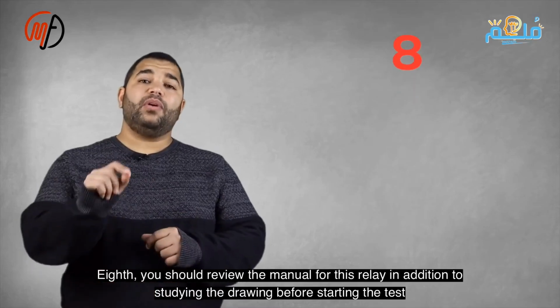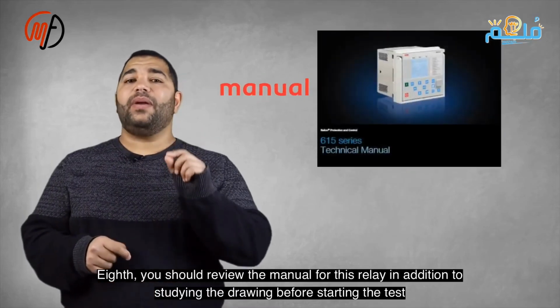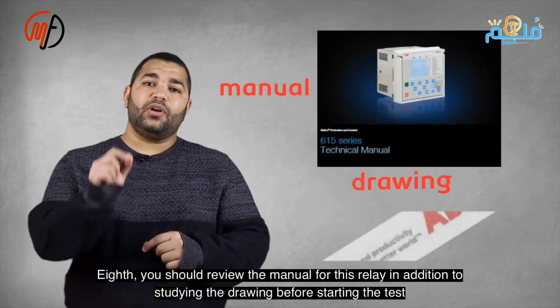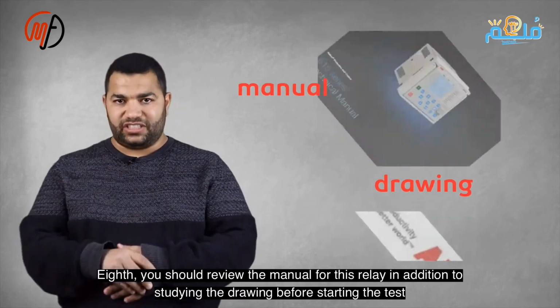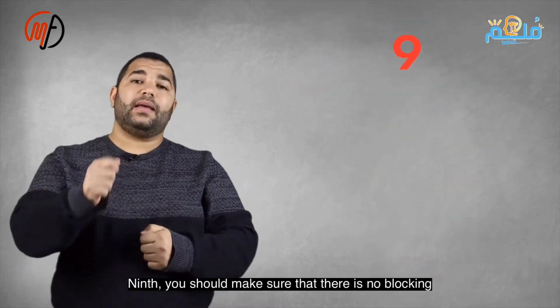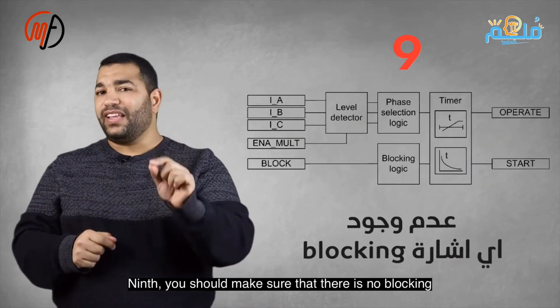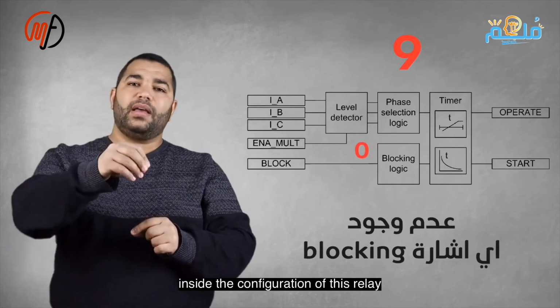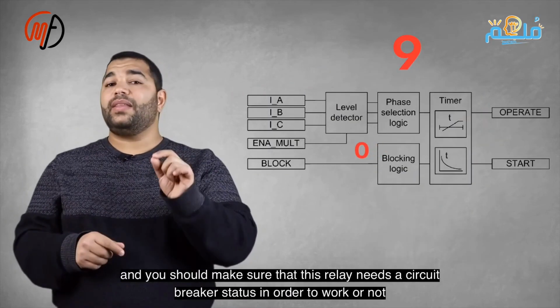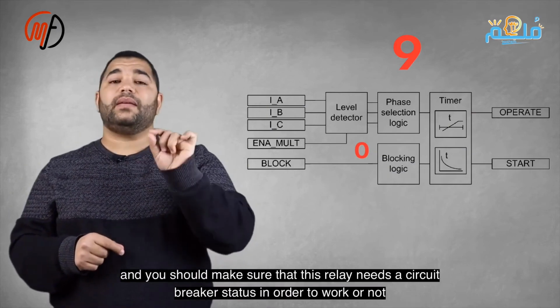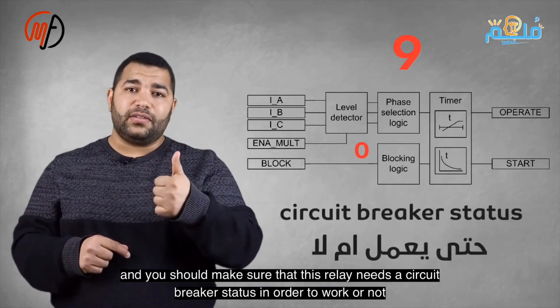Eighth, review the relay manual and study the drawings before testing. Ninth, ensure no blocking signals in the relay configuration and check if a circuit breaker status is needed. 10th, if the relay reads incorrect current values, verify if the panel and injection device grounding points are the same. If so, separate them to prevent current loss.